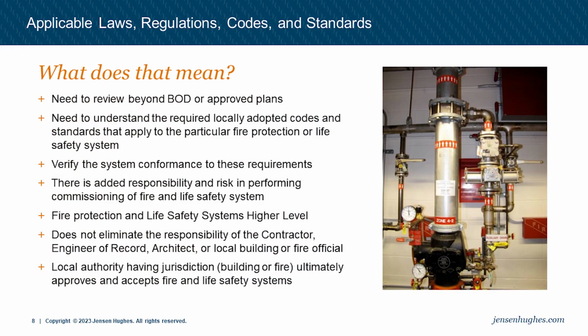So what does applicable laws, regulations, codes, and standards mean, and how do you make sure you comply with that? Well, it means you need to review beyond the basis of design, the approved plans, or the OPR. You need to understand the required locally adopted codes and standards that apply to the particular fire protection and life safety system, and verify the system's conformance to these requirements.